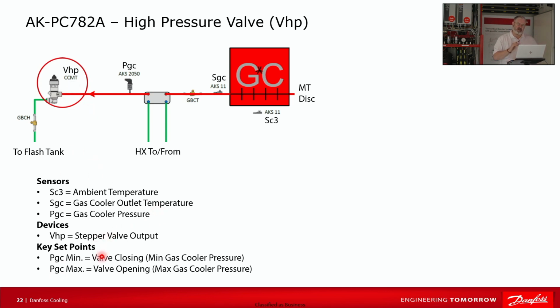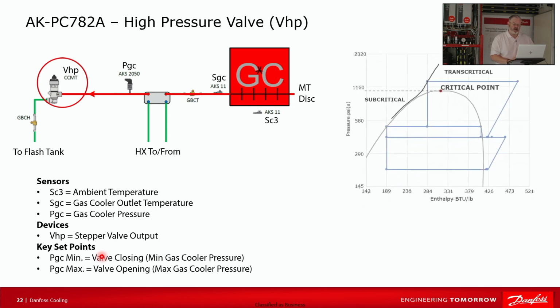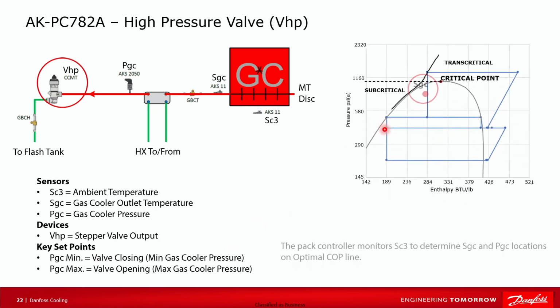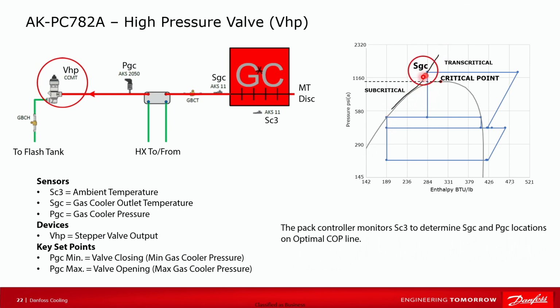But if you'll notice, we didn't tell it where it should be at. And some people call this the magic valve. That's why they call it that, because there's no defined set point, just a minimum and a maximum. And the reason for that is this COP line here. So there's a line on this chart here.